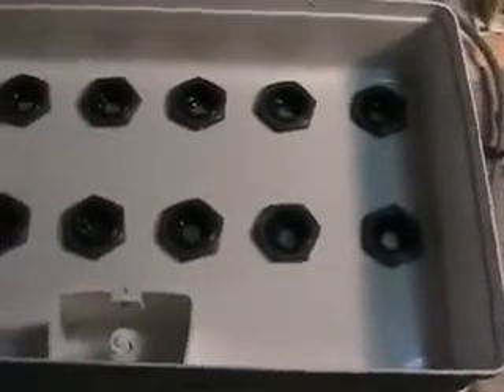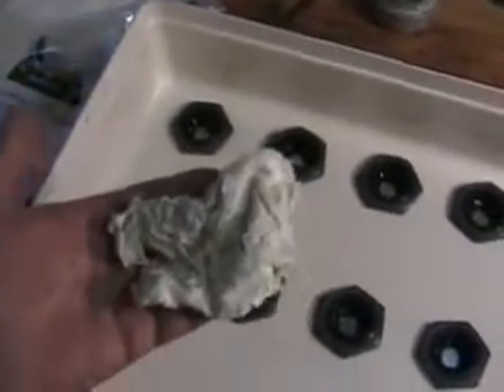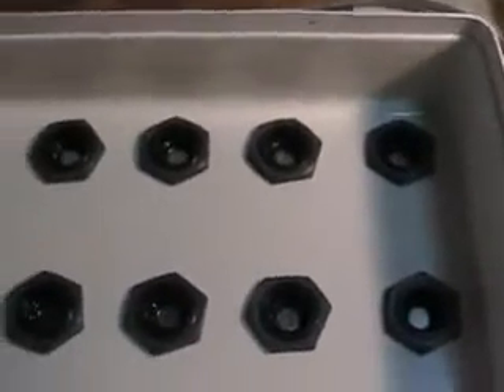We started this tape at about 5:45, and it's now just a little before 6. Two tissues and three Q-tips later, we have a clean pan. I don't think you'd have had to clean it, but since we're changing this transducer, I wanted it nice and sparkly. The point is, it takes very little time to clean this up if you want to. Now let's change out the transducer.